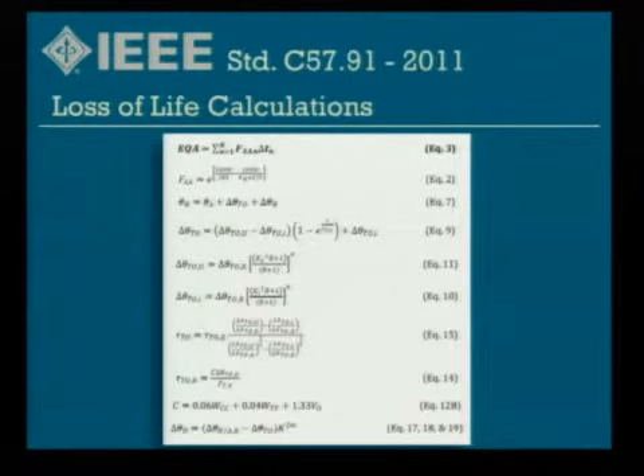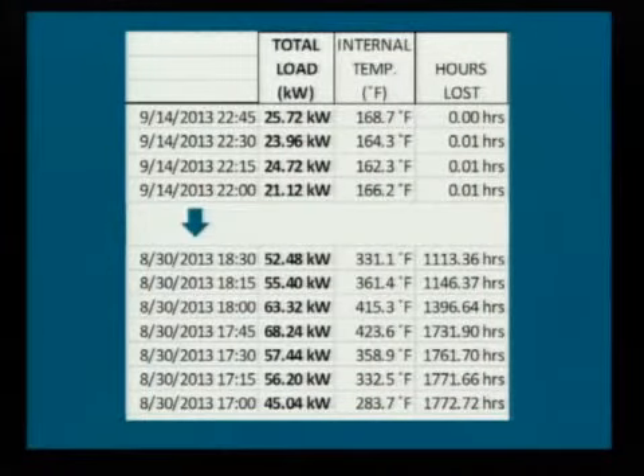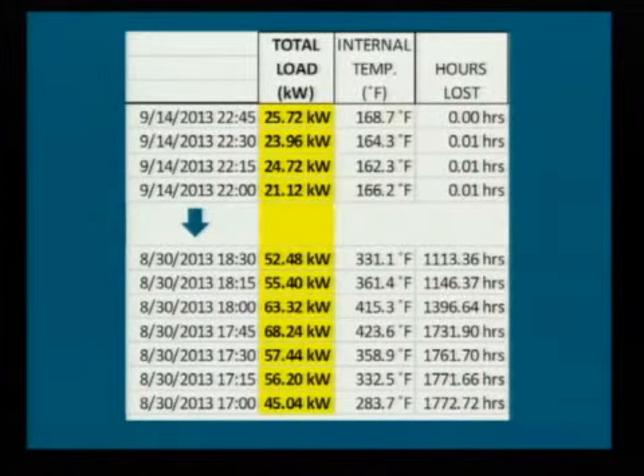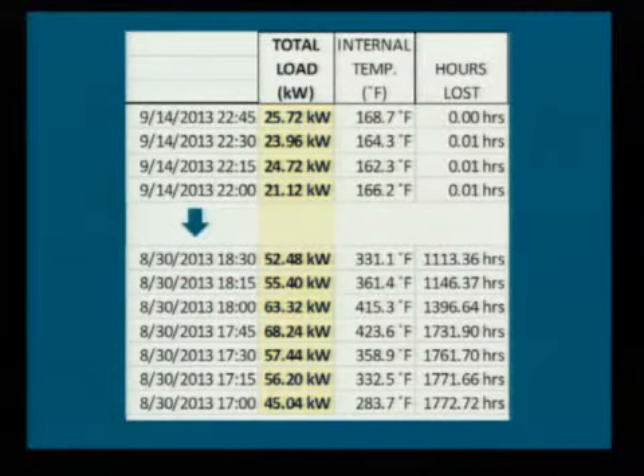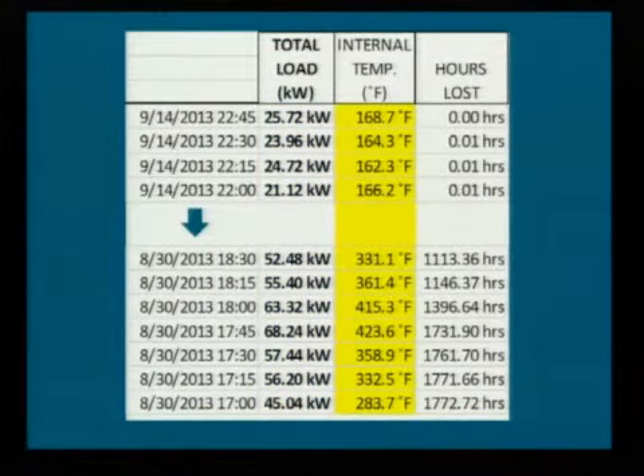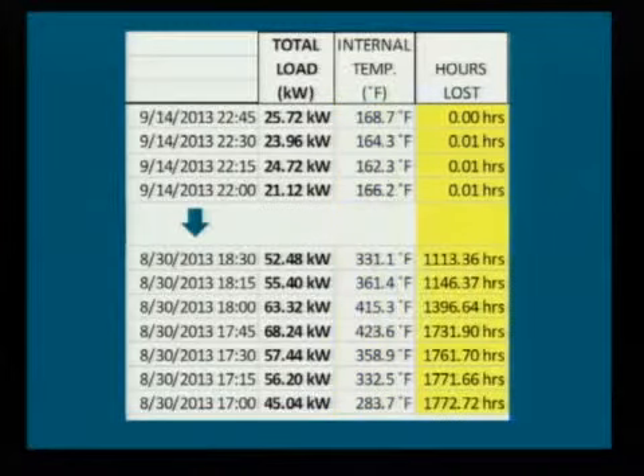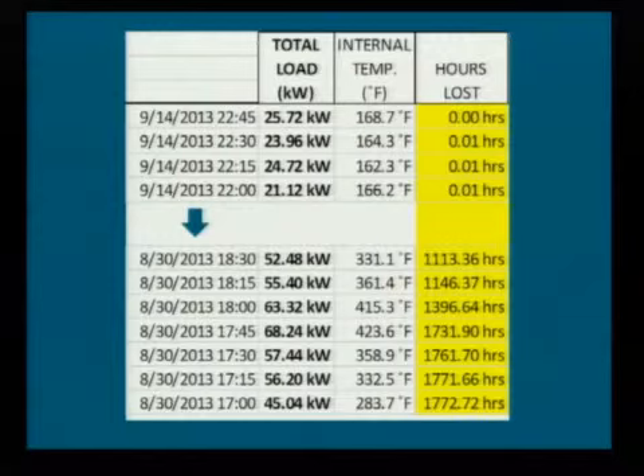I won't bore you with the calculus, but basically this allowed us to calculate, based on how stressed the transformer was, how fast it's aging and degrading. For every 15-minute interval, we could calculate how much load's on the transformer, how hot it's getting, and predict how fast the transformer is actually degrading at each interval.